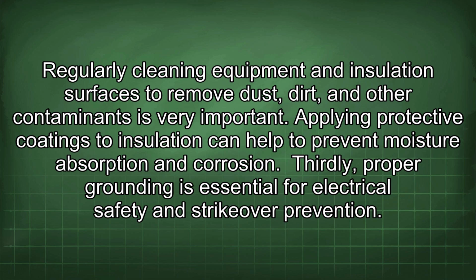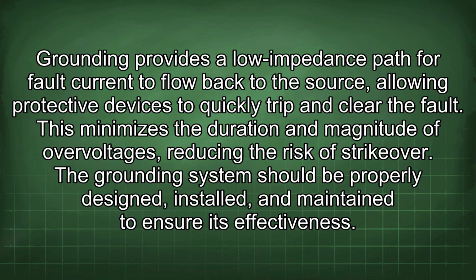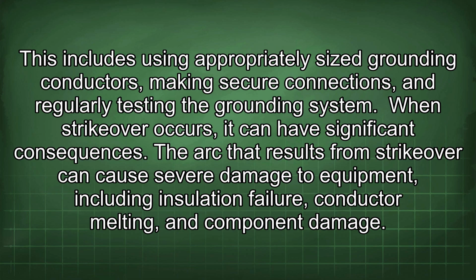Thirdly, proper grounding is essential for electrical safety and strikeover prevention. Grounding provides a low impedance path for fault current to flow back to the source, allowing protective devices to quickly trip and clear the fault. This minimizes the duration and magnitude of overvoltages, reducing the risk of strikeover. The grounding system should be properly designed, installed, and maintained to ensure its effectiveness. This includes using appropriately sized grounding conductors, making secure connections, and regularly testing the grounding system.